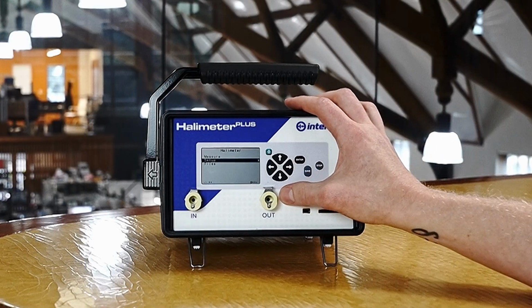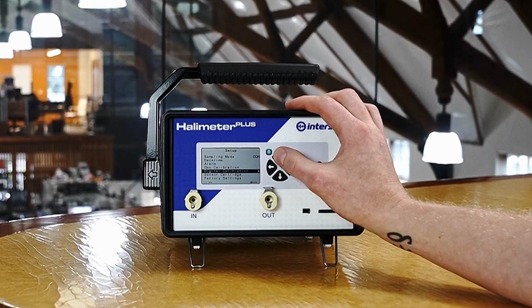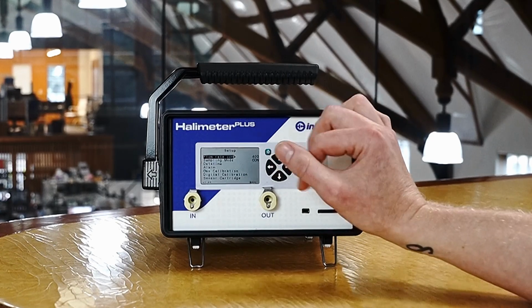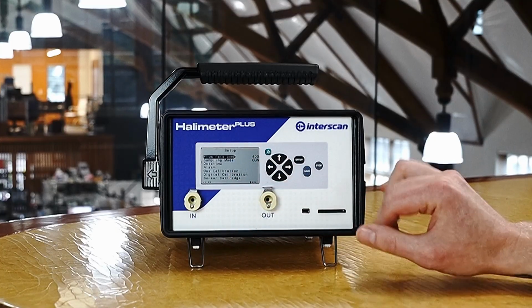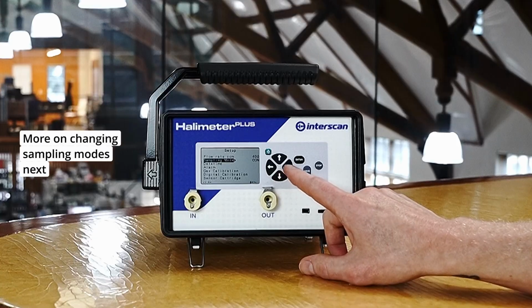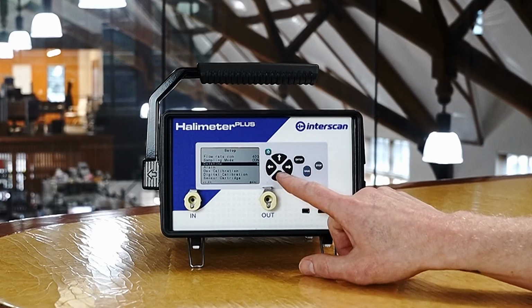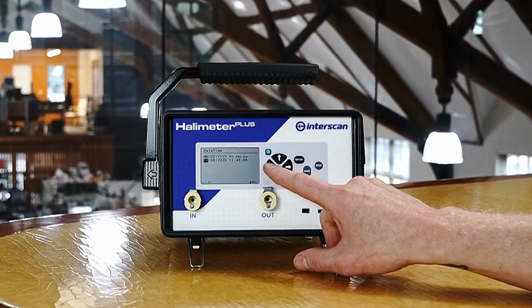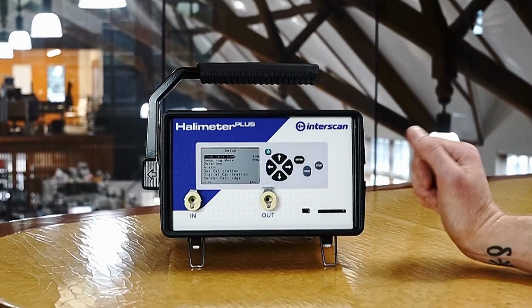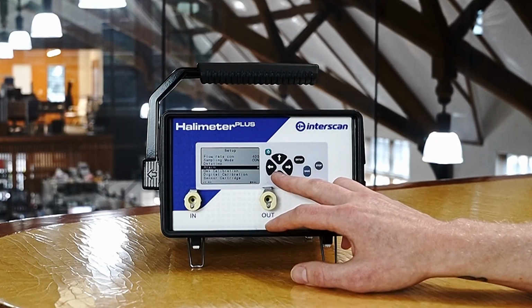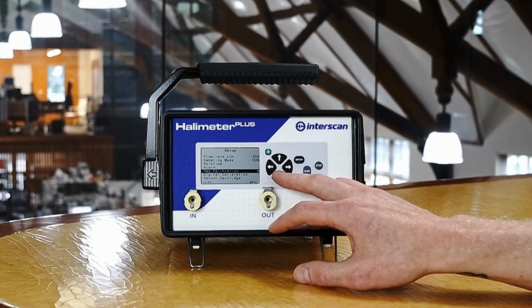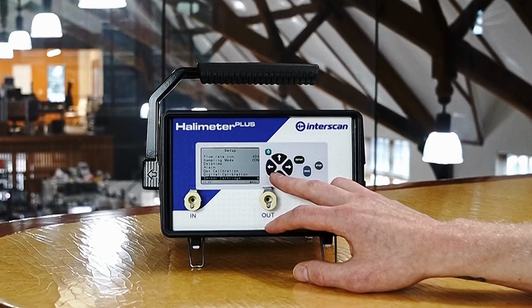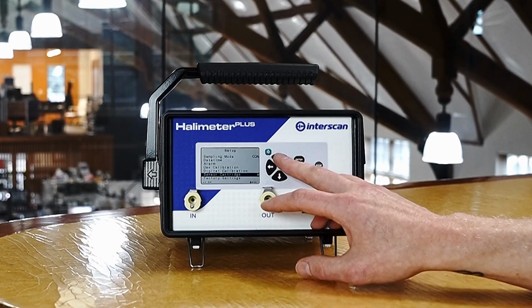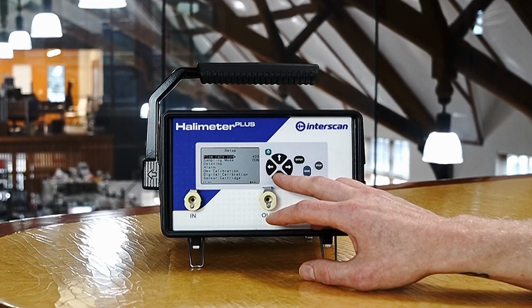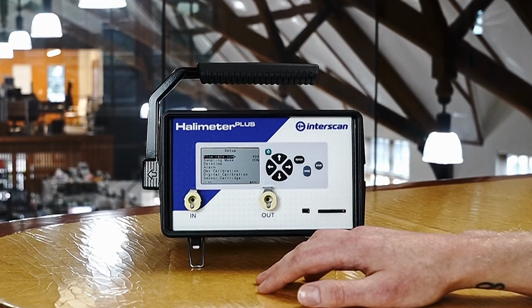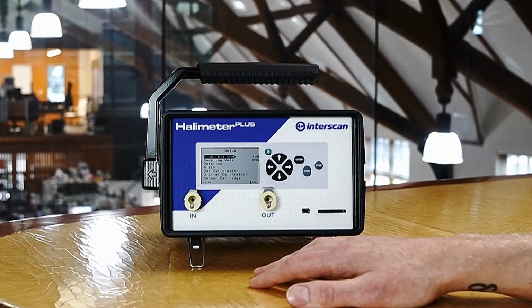When you receive your device, you can go through the setup menu and you'll see that specific values are already input. For example, your flow rate is set according to your calibration, so you should not change this. You can change your sampling mode from constant to Halimeter, and you can also set your date and time through this menu, as well as your alarm level. In the setup menu, there are a few options meant for internal use only — they're here as a reference: gas calibration, digital calibration, sensor cartridge, and factory settings. Typically, you won't need to change anything in the setup menu other than your sampling mode. If you have any questions about the various functions in the setup menu, feel free to reach out to us.